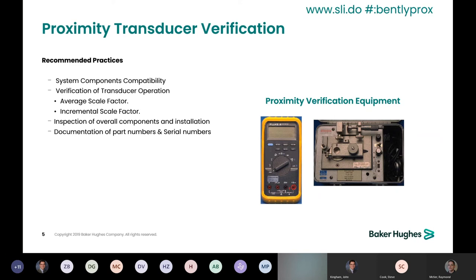It's also good practice to perform an inspection of the physical components. Some of the inspection items include the proper gap, the use of connector protectors, the use of the safety lock wire, the state of the click lock connectors, and the field wiring termination.